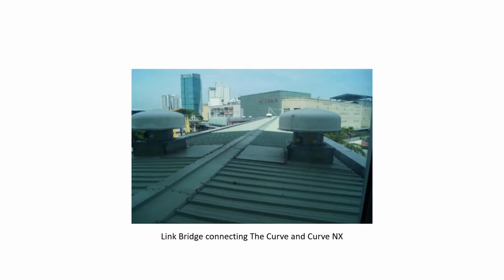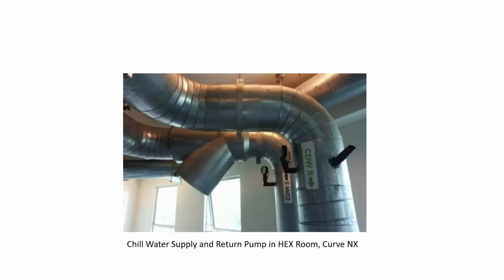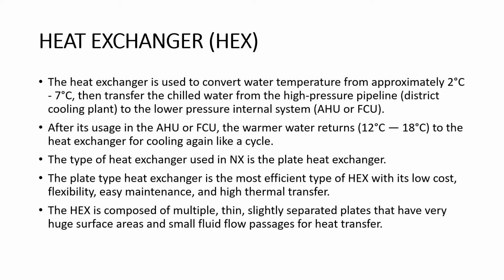So the picture shows the link bridge connecting to Curve NX. And this picture shows the chilled water supply and return pump in the heat exchanger room, Curve NX. So the heat exchanger, HEX, is used to convert water temperature from approximately 2 degrees Celsius to 7 degrees Celsius.